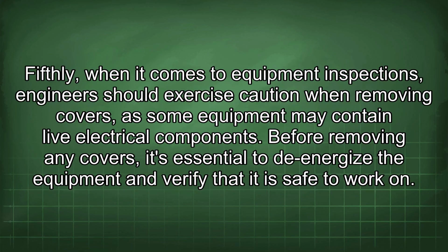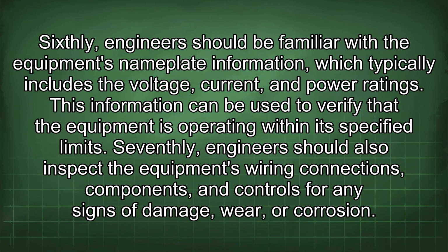Fifthly, when it comes to equipment inspections, engineers should exercise caution when removing covers, as some equipment may contain live electrical components. Before removing any covers, it's essential to de-energize the equipment and verify that it is safe to work on. Sixthly, engineers should be familiar with the equipment's nameplate information, which typically includes the voltage, current, and power ratings. This information can be used to verify that the equipment is operating within its specified limits.